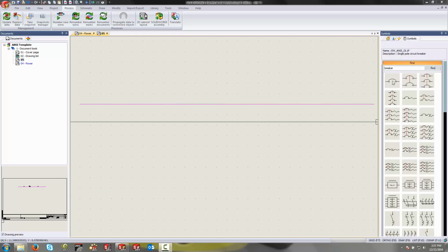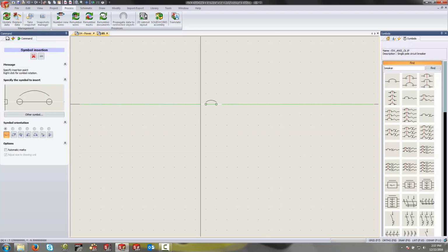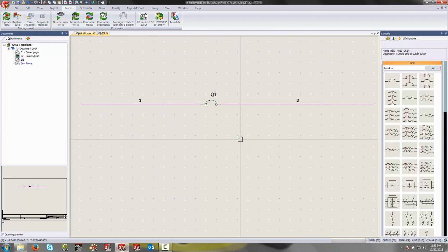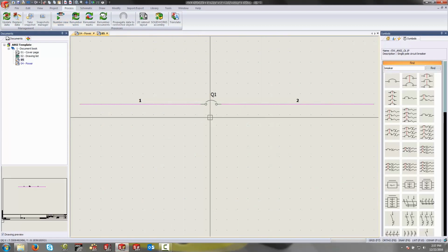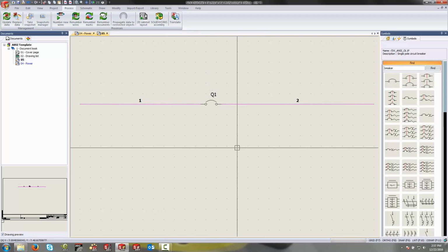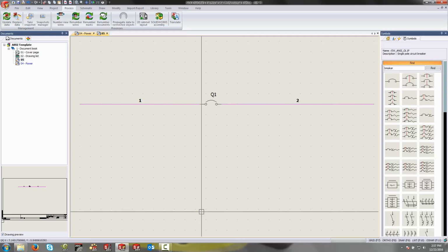So when you place a symbol on top of a wire inside of SOLIDWORKS Electrical, very commonly what will happen when you go to number the wires is that each individual wire that's connected to that will be given a different equipotential label. But what if you wanted to pass that equipotential label through this circuit in order to maybe transmit that particular signal to some further destination down the line? This is pretty common if you have inline connectors or even terminals. So that's exactly what I want to talk about, is how you can configure your system to do that and where those options are located.